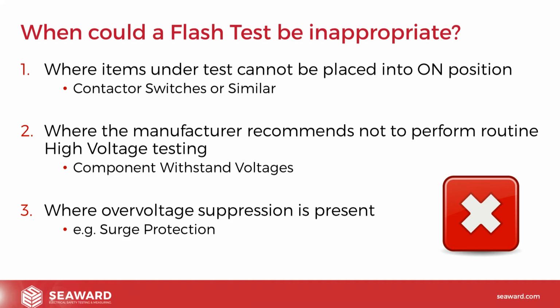So if we receive information not to perform such a test, then we should always go with the manufacturer's guidance. And hopefully the test that we talk about today will give you an alternative method to ensure that your customers are safe. And the third instance where we may not be able to flash test is if we have something called overvoltage or overvoltage suppressants.